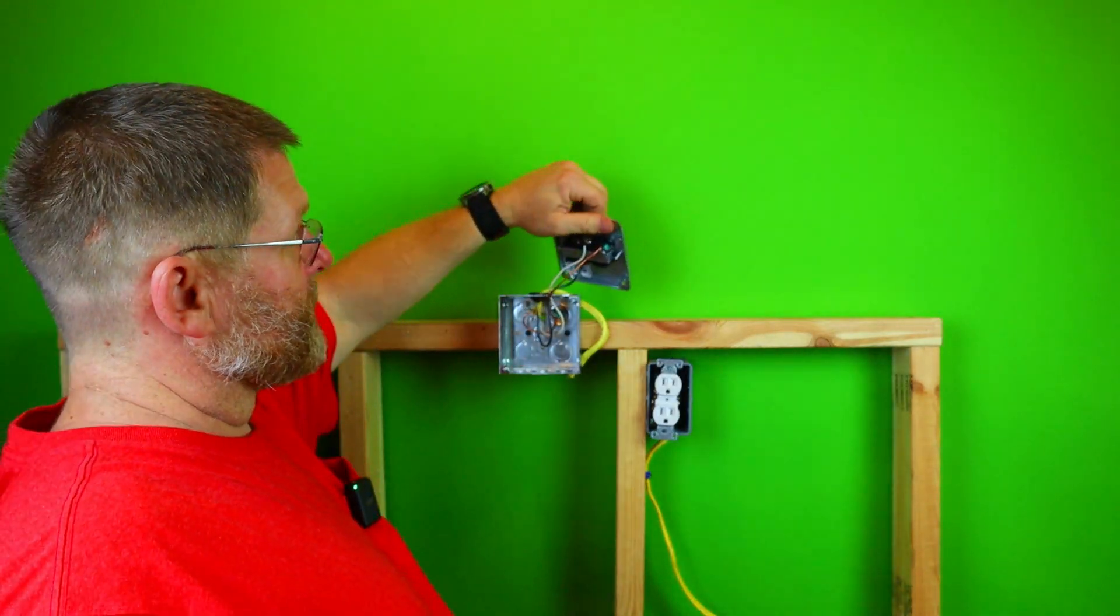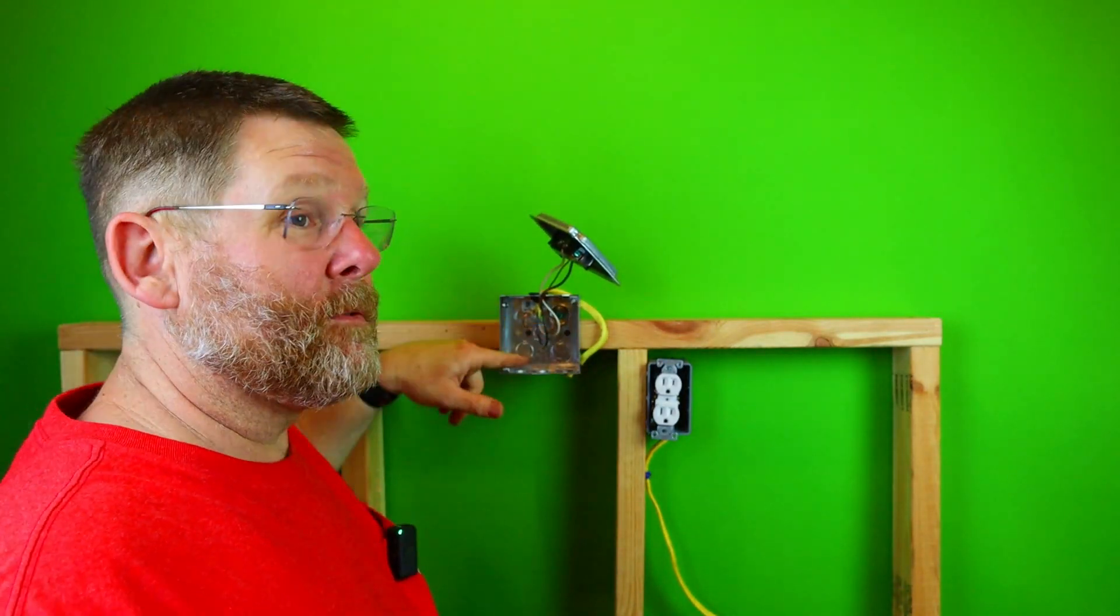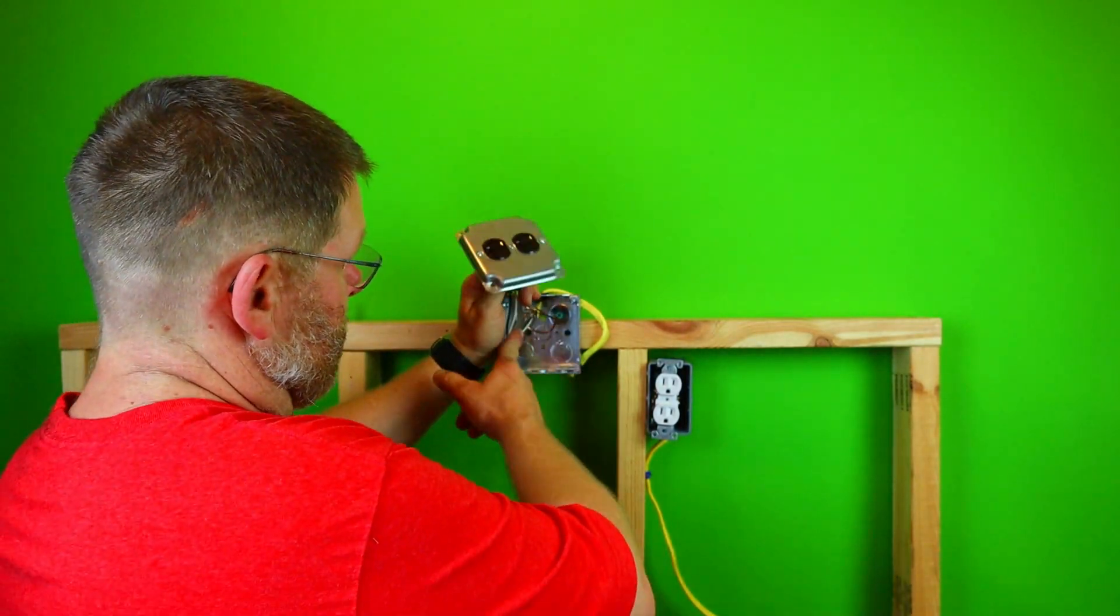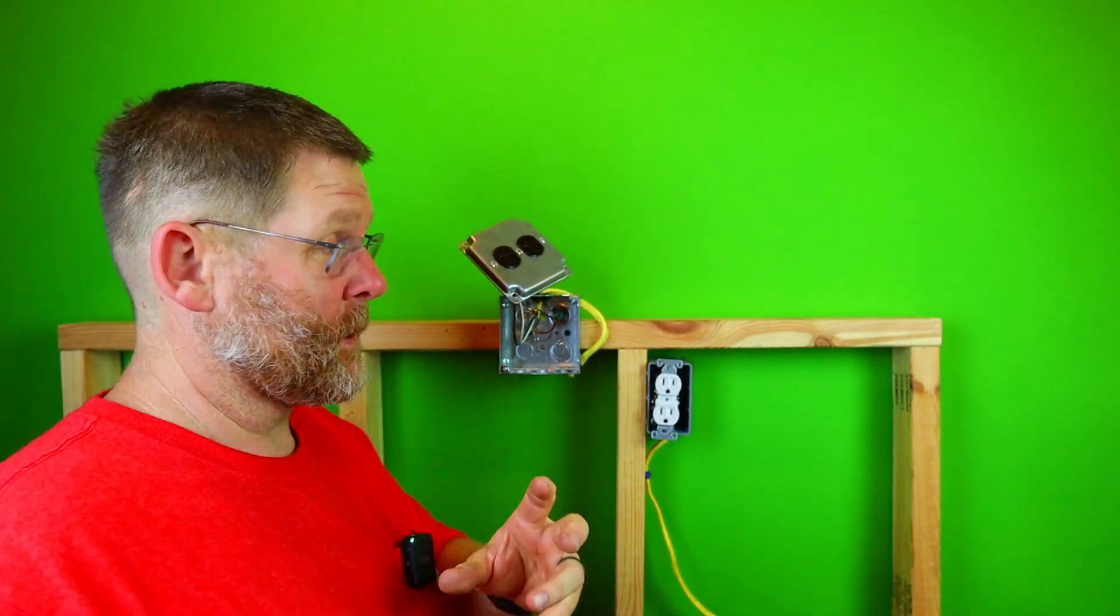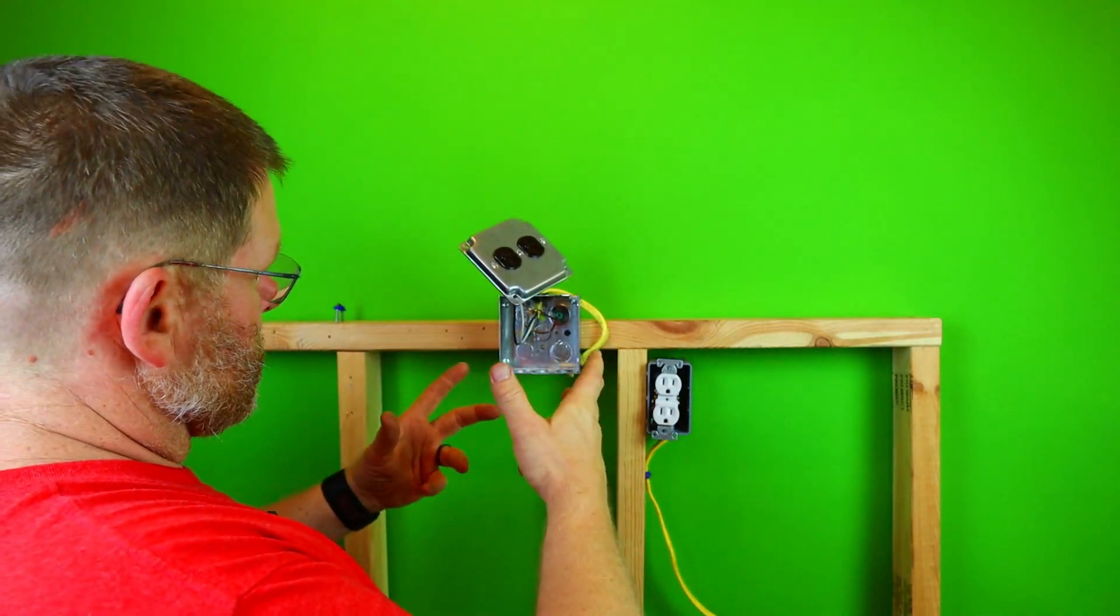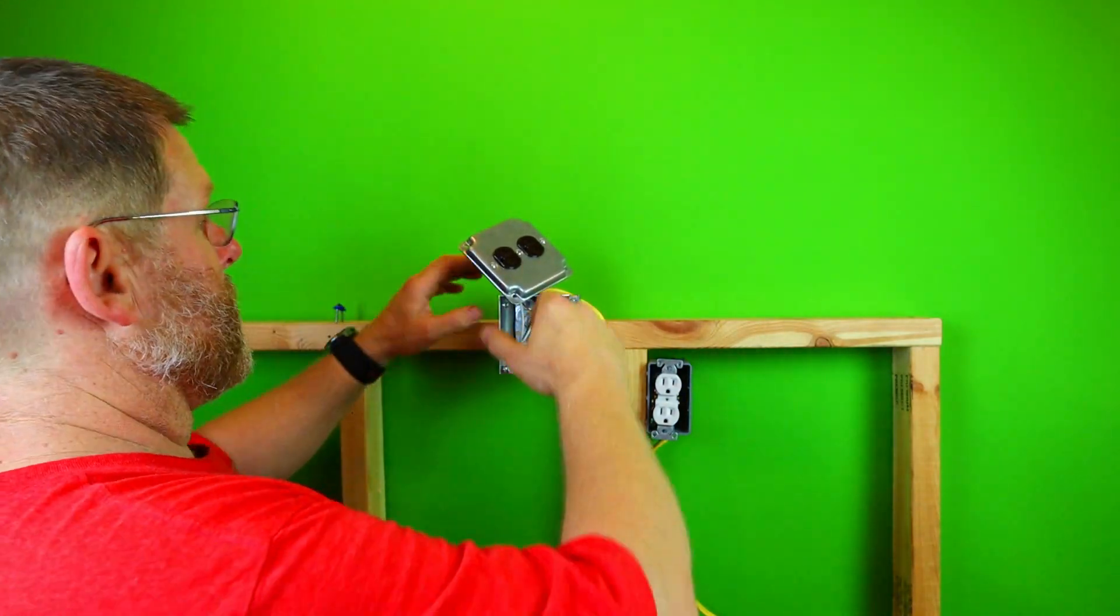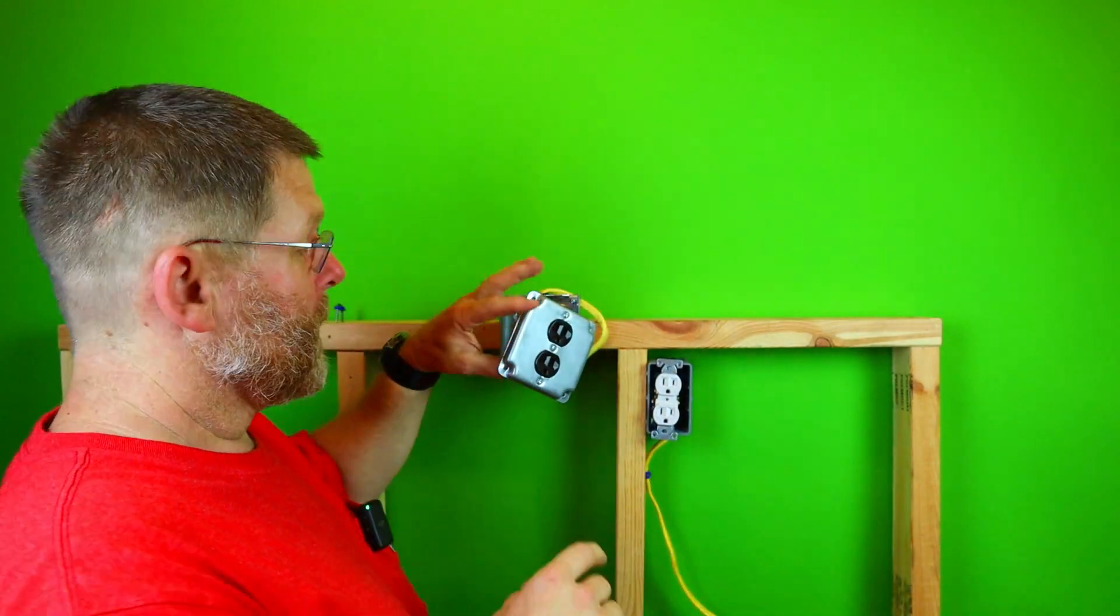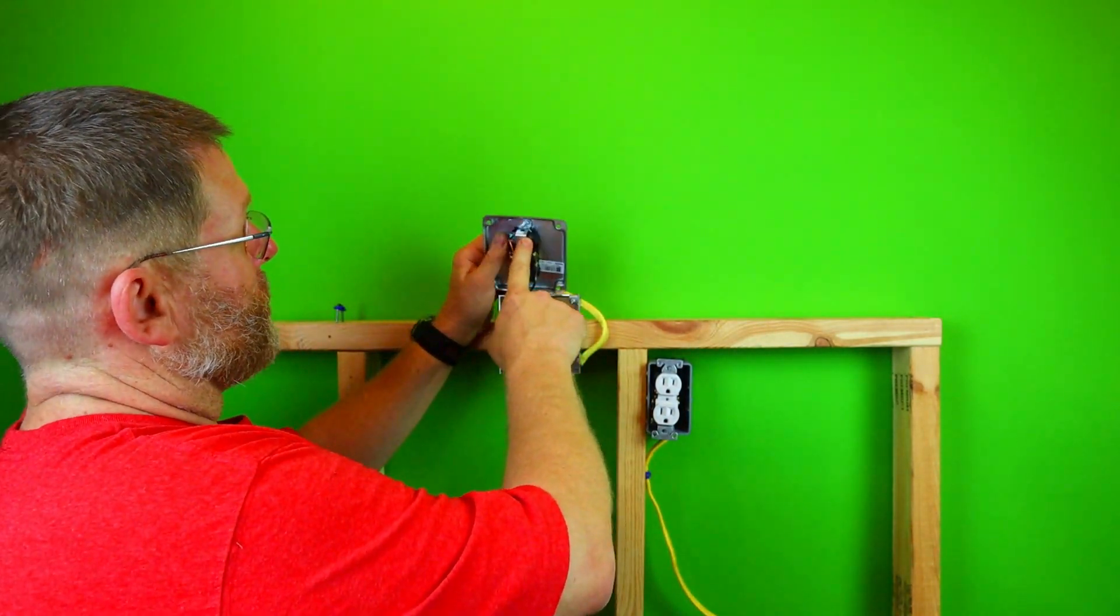So do you? Well, code says if you use a self-grounding receptacle, you do not have to ground the box. As you see, I did, and let me tell you my reasoning. So the whole reason why you technically don't have to is because after you put this into the box, right, you have a self-grounding receptacle.